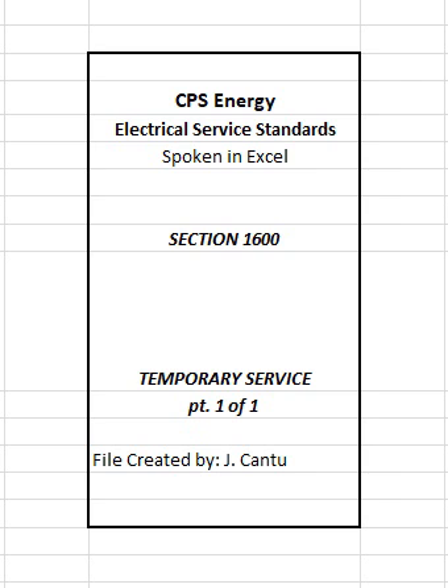1603.1 Location of temporary meter structure. The structure shall be located within 2 feet and in line with the rear of the supplying transformer's pad. It shall be constructed with the meter positioned to face the street or alley. Transformer lid padlock is always located on the front of the transformer. Refer to Figure 1601. Where transformer is located on an adjacent property and the property owner objects to the temporary meter loop, it may be moved to adjoining undeveloped property utilizing CPS Energy's easement, but as close to transformer as possible. The temporary meter loop shall face towards the street or alley.